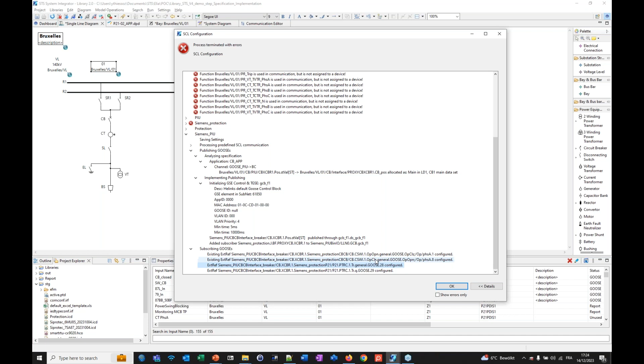For the Siemens PIU, we also subscribe to some GOOSE. For example, here you see that we reuse two existing ExtRefs, the operation close and the operation open, which were information in the process ICD file that we have used. For some others, we just create the ExtRef because it was not predefined in the process ICD.